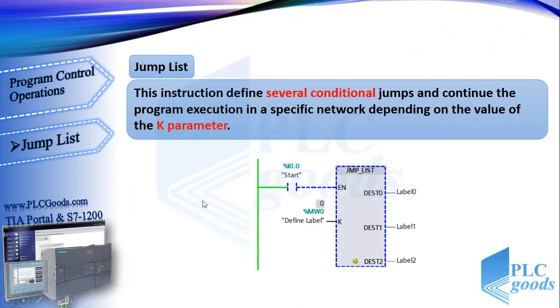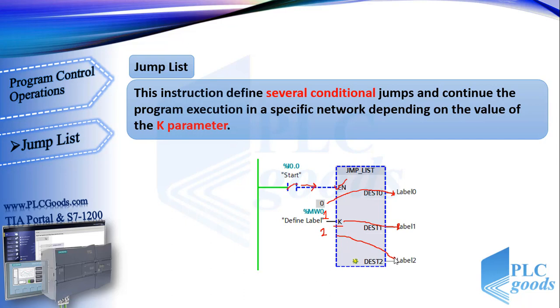Let's see the next instruction: jump list. This instruction defines several conditional jumps and continues the program execution in a specific network depending on the value of the K parameter. The destination network must be identified by a label. At this program, first we need to activate the start contact. Now the K parameter value is zero, so the program jumps to the destination network with label zero. If the K parameter value was one or two, the program jumps to the network with label one or label two. We can increase the network destination up to 32.